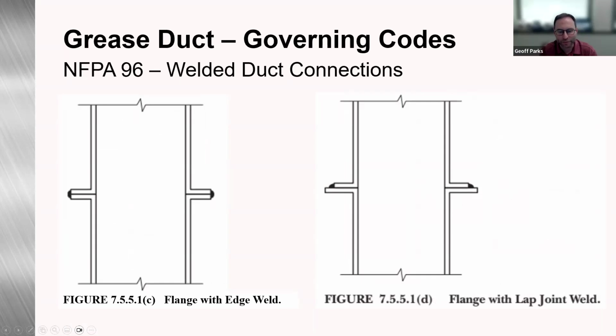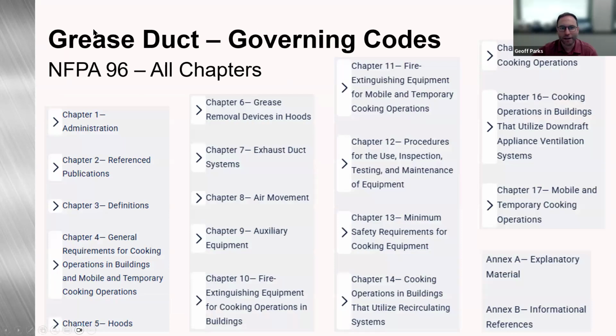Also out of NFPA, we have the flange with the edge weld, and this is going to be a maximum of a 1/2 inch flange. And then there's also a flange with a lap joint weld. What that means is basically the 1/2 inch plus a little extended flange for welding purposes. So they're calling that the flange with lap joint weld. And here's all the chapters out of NFPA 96. Not going to get into all that, but there's quite a bit of information available at NFPA.